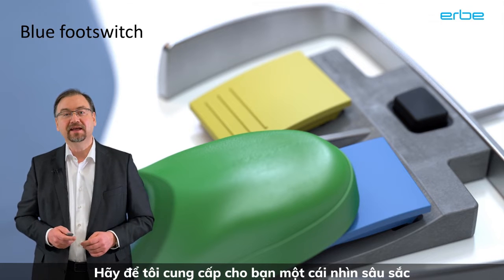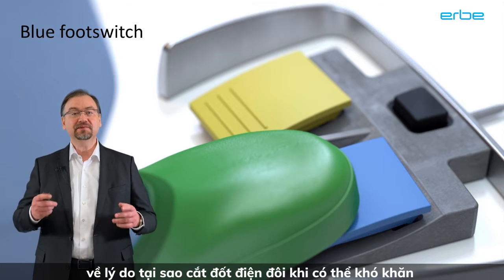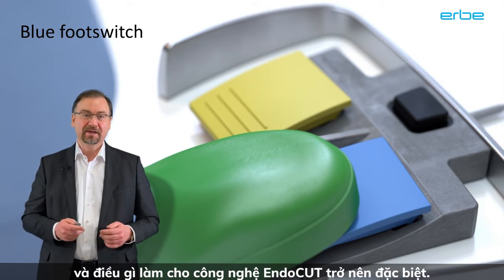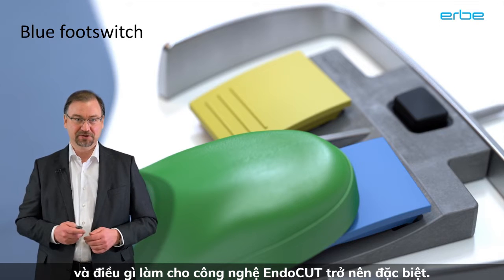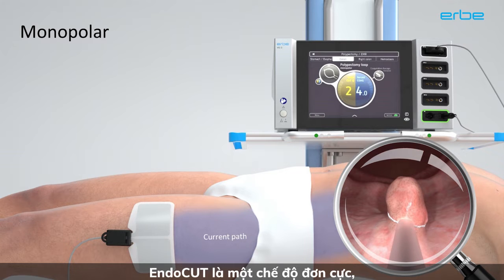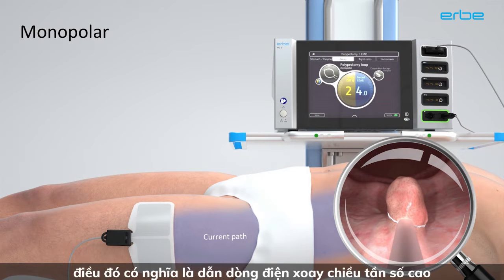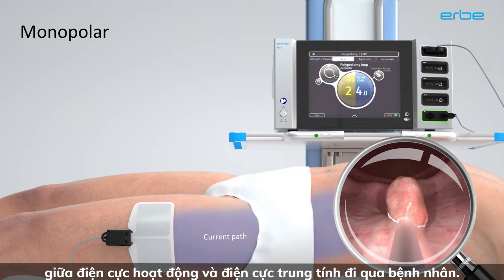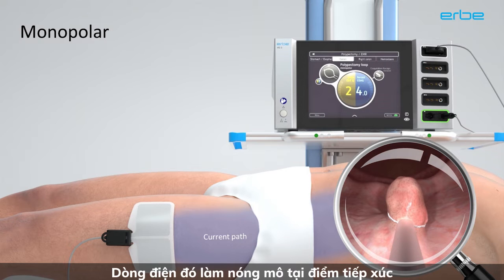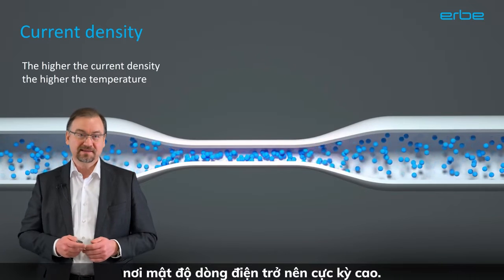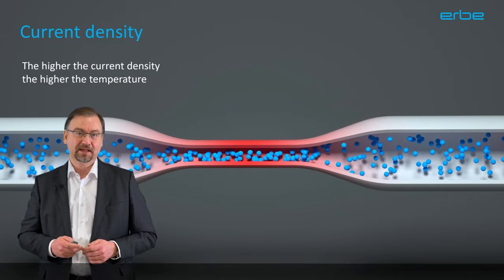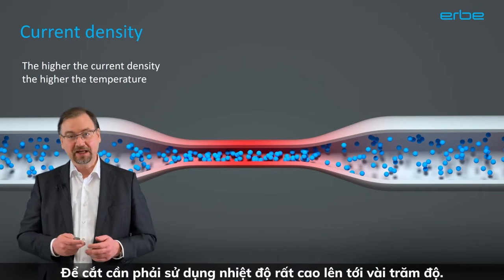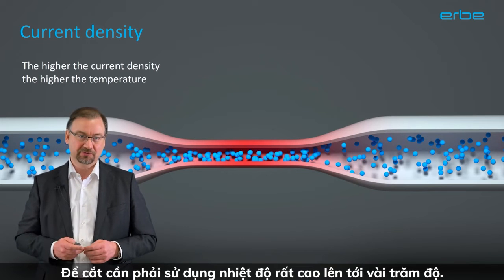Let me give you an insight in why electrosurgical cutting sometimes can be difficult and what makes the EndoCut technology so special. EndoCut is a monopolar mode, which means that you conduct high-frequency alternating current between the active and the neutral electrode through the patient. The current serves to heat the tissue at the point of contact, where the current density becomes extremely high. For cutting, you need very high temperatures of several hundred degrees.